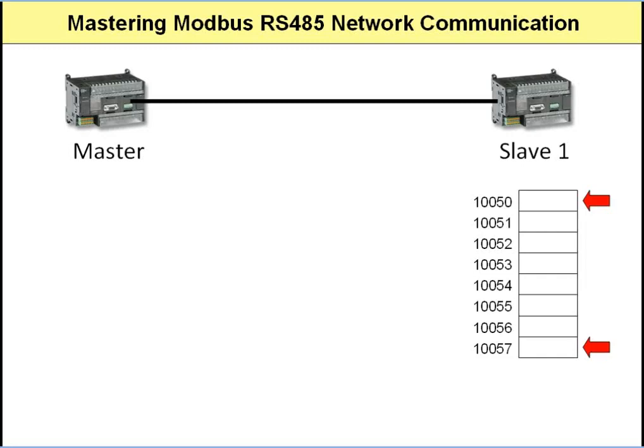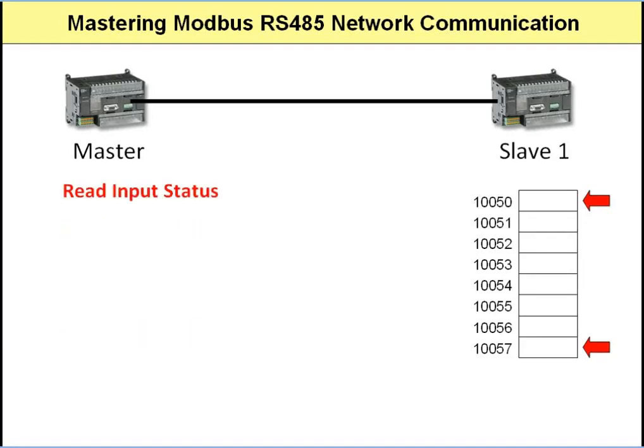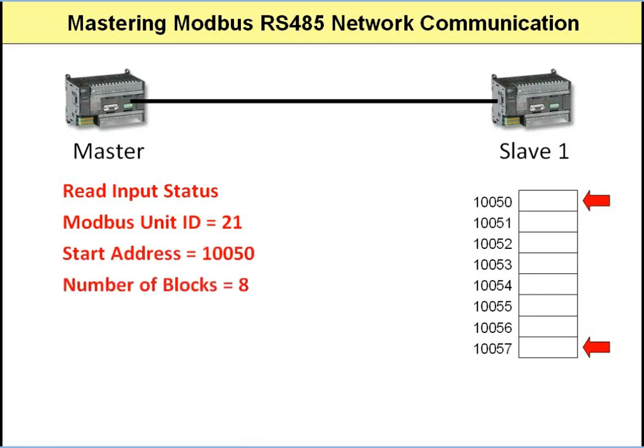The read input status command only allows you to specify a start block address and then the number of memory blocks to read from the start point. So in this example, you would configure the Modbus master to send the read input status command with the Modbus unit ID of 21 — those are correct — but instead of specifying 10,050 and 10,057 individually, it would specify a start memory address of 10,050 and a memory block length of 8. Remember this — it's extremely important.